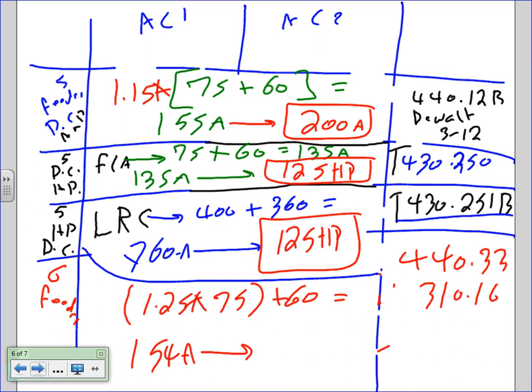This got another change here, name from last year. So this has become table 310.15B16. If you go there, it will give you 3 conductors, number 2 aught. Have you guys noticed that I use 3 conductors all the time with equipment? The default is 3. Unless you know they need a neutral, you always default to 3. Why 3? 3 phase. That's piece of cake.